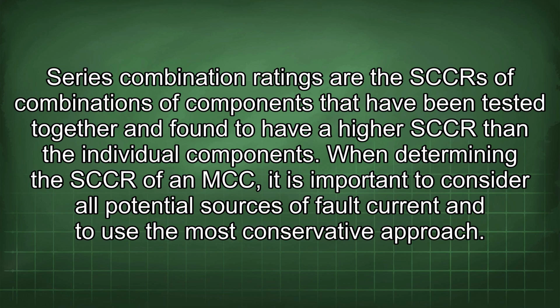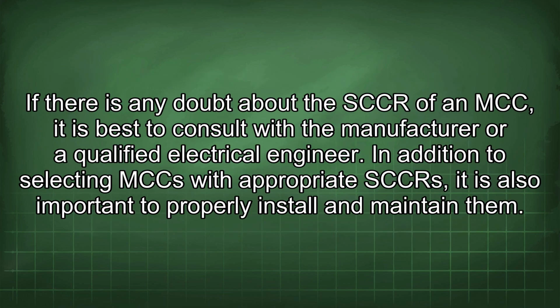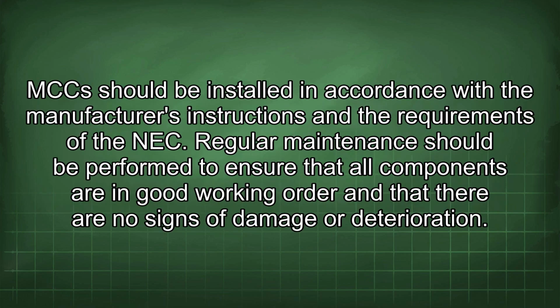When determining the SCCR of an MCC, it is important to consider all potential sources of fault current and to use the most conservative approach. If there is any doubt about the SCCR of an MCC, it is best to consult with the manufacturer or a qualified electrical engineer. In addition to selecting MCC with appropriate SCCRs, it is also important to properly install and maintain them. MCC should be installed in accordance with the manufacturer's instructions and the requirements of the NEC. Regular maintenance should be performed to ensure that all components are in good working order and that there are no signs of damage or deterioration.